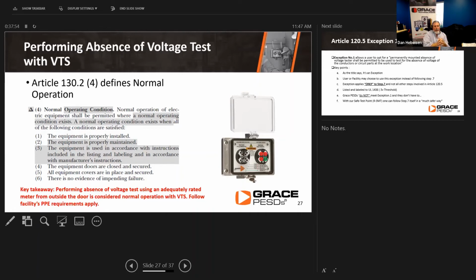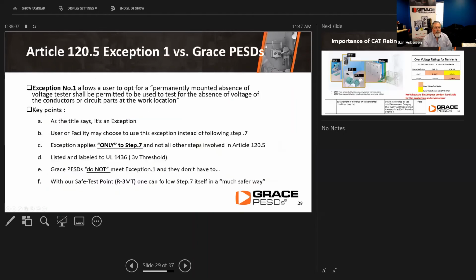And this is really gaining in popularity because it is very efficient and is such a valuable tool as far as reducing exposure and risk hazard. So that's why it's really becoming quite popular. There's a little bit of conversation taking place. We talked earlier about the new exception number 1, which allows the user to opt for a permanently mounted absence of voltage tester. And that is permitted to be used to test for the absence of voltage.